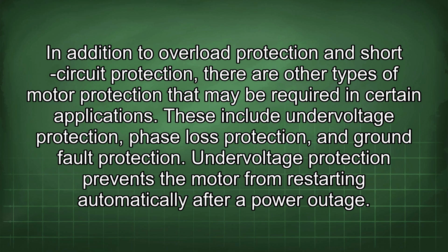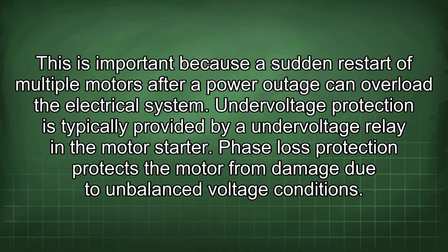These include undervoltage protection, phase loss protection, and ground fault protection. Undervoltage protection prevents the motor from restarting automatically after a power outage. This is important because a sudden restart of multiple motors after a power outage can overload the electrical system. Undervoltage protection is typically provided by an undervoltage relay in the motor starter.